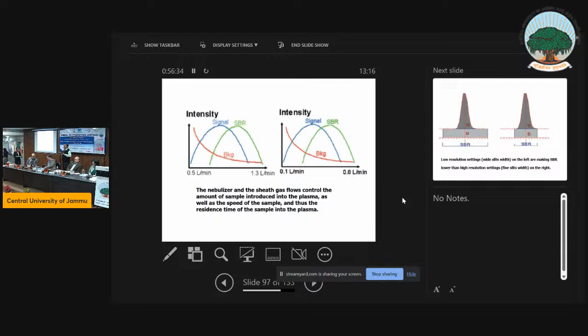Then there is low resolution and high resolution, and the signal to background ratio. What happens is that when you are checking the signal, there is a peak coming like this, and your focus is on the peak only. Then the next time when this peak comes like this, you will be more happy. And of course you should be, because the numerical number is also high, the peak height is very high. Please don't do that. Along with that peak height, always focus on where this line is moving. You have increased intensity by 10 times, but background increased by 12 times. So the signal to background ratio is dropping down. You have to maintain the signal to background ratio from the calibration to the end of the analysis.